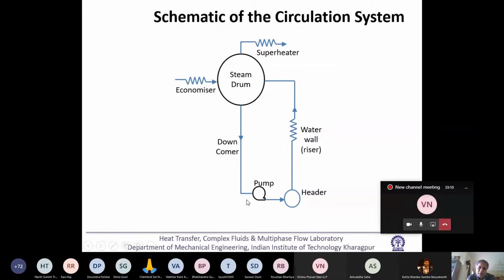And this is a very important feature of a subcritical boiler. When a boiler is working in the subcritical condition, within the two-phase dome, this is a very important feature. And there are three parts. In the economizer, heat is transferred to water. In this circulation loop, water is getting converted into steam, and in the superheater, the saturated steam is getting superheated. Okay.